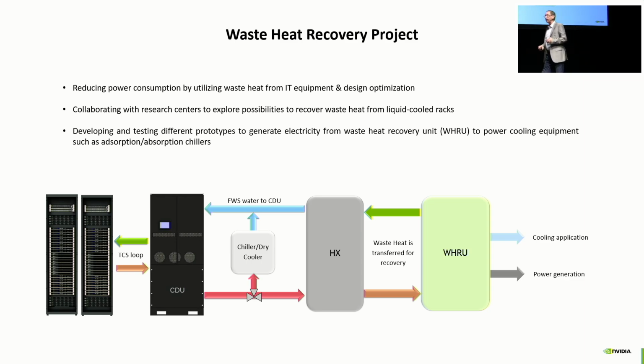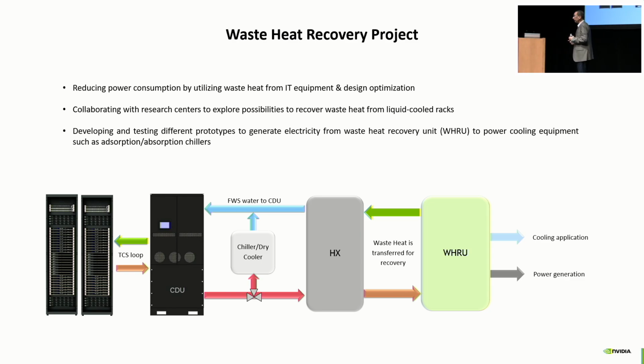If it goes to 85, 80 degrees C, something above 60 or 70 degrees C, I can run absorption chillers, and I can use fuel cells. I can use heat rejection away from traditional heat reuse like district heating, which is well known. I can have a data center anywhere in the world that doesn't require district heating like Nordic regions, but I can develop data centers that produce electricity based on waste heat, and run that waste heat as a supplement to an absorption chiller to produce cooling.